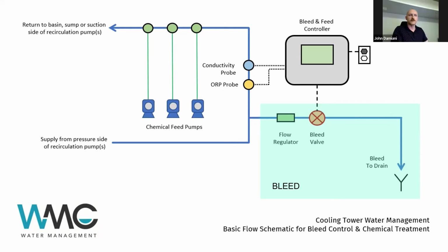But the new water coming in is going to be fresh city water or fresh makeup water, which has that lower concentration of all these minerals. And that's how we keep it under control. This is an automatic system that keeps doing that. So it's usually a motorized valve or a solenoid valve that'll open, be controlled through a flow regulator, so we bleed at the right rate. And that's the first stage of the program. The second stage of the program is feed. So we often call these a bleed and feed system.